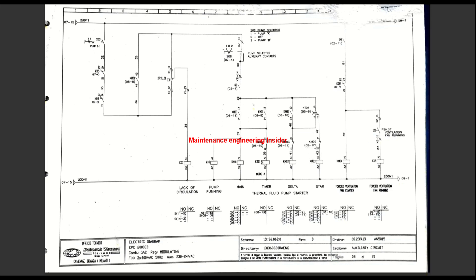If you want further information — for example, if this contactor coil is not coming in — you can put your multimeter here and check if voltage is present. If the switch is closed and the circuit breaker is not open, you should have 240 volts here. If you don't have 240 volts between these two points with your multimeter, you narrow it down and check whether the timer is okay and functioning as it should.